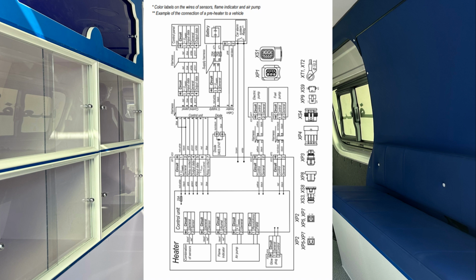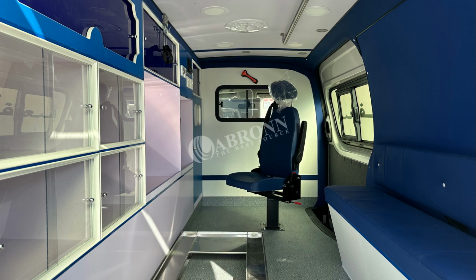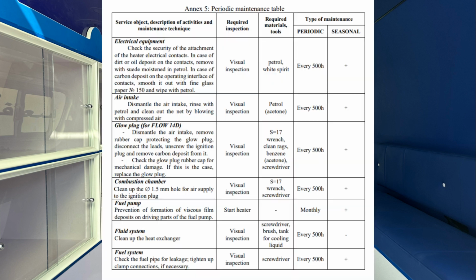3. In case of overheating of the heater coil, for example due to a blocked intake or output of the heating unit, the heater automatically switches off. 4. If the maximum temperature of the heated coolant is exceeded, for example, due to air trapped in the coolant system, the heater automatically switches off.